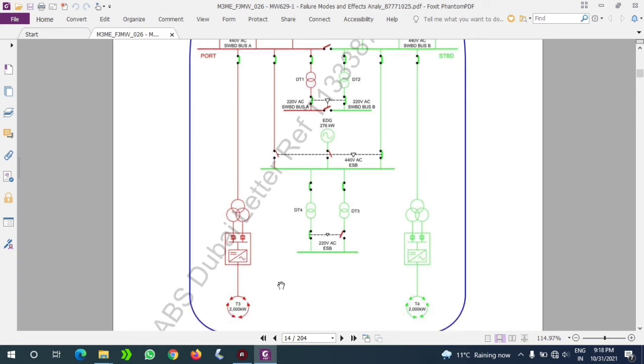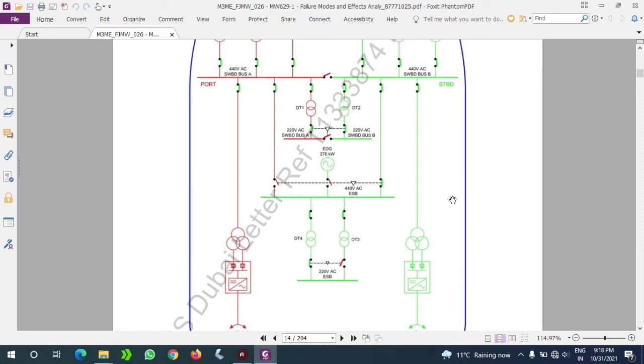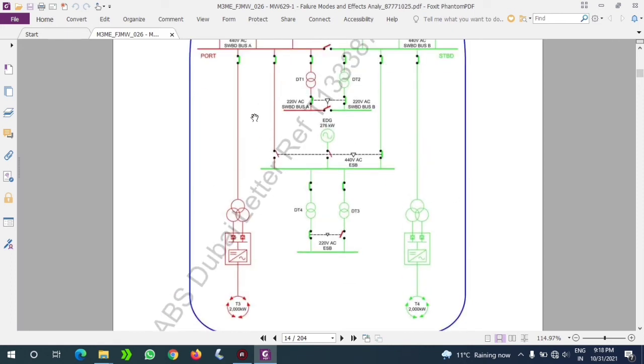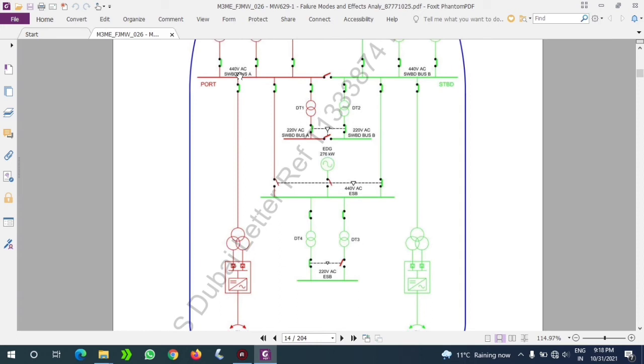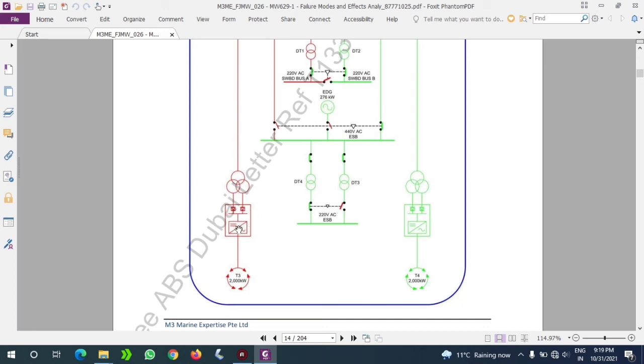Now what are these two power connections? I have already told that we have two giant thrusters, each of 2000 kilowatt. How is this guy going to run? He needs enormous power. For that it is directly connected to the 440 volt bus bar. So you should check the rating - one thruster itself is taking the power of 2000 kilowatt, which means that one generator itself cannot supply power to that thruster. So we should always run two generators in parallel in order to make one thruster start. This is the basic idea.